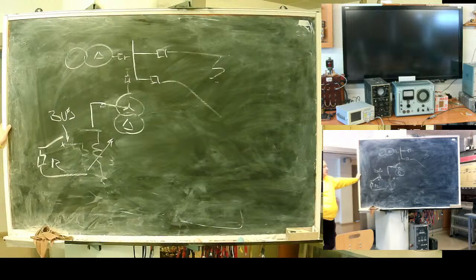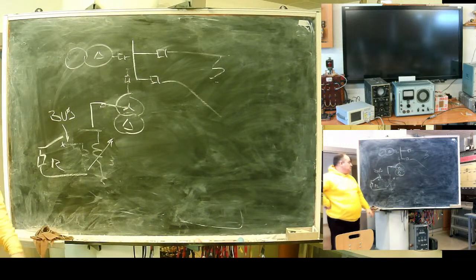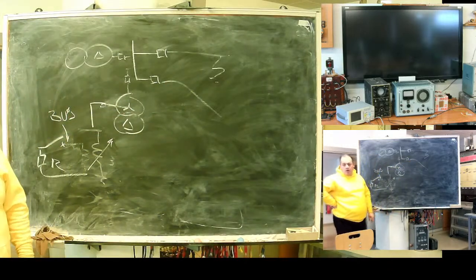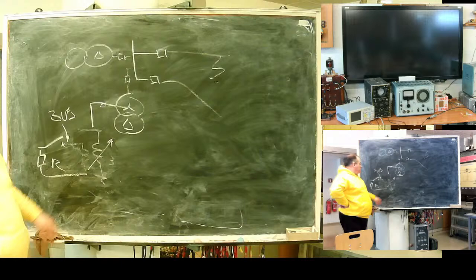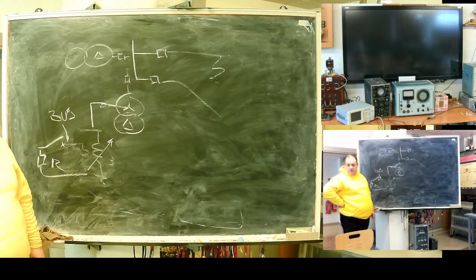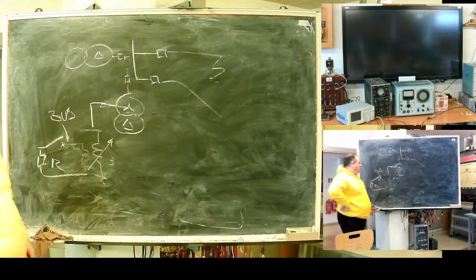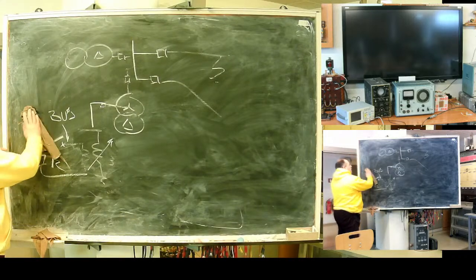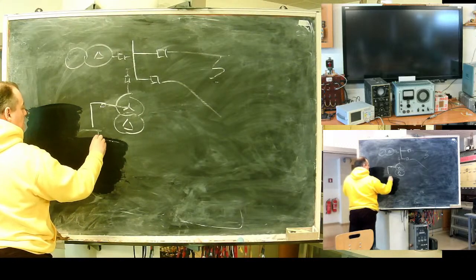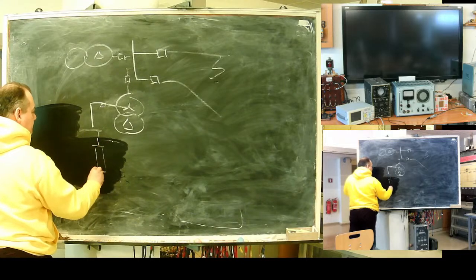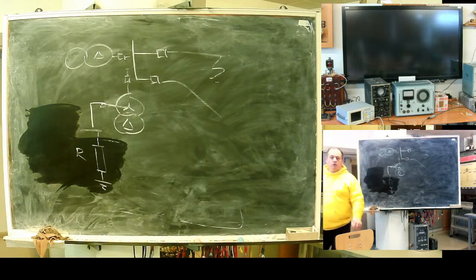For small networks with small capacity and small fault current, installation of the complete set is too expensive. So there can be a cheaper version. In the cheaper version, only a resistor is installed, so-called high ohm neutral. They look like a space frame with wire around.